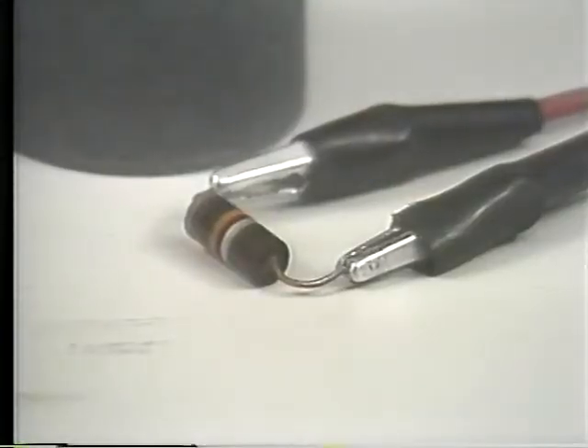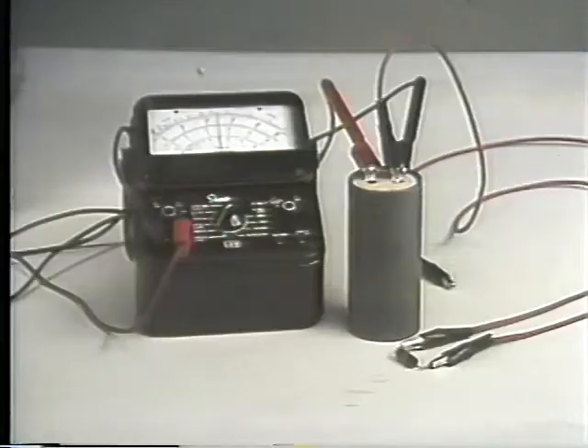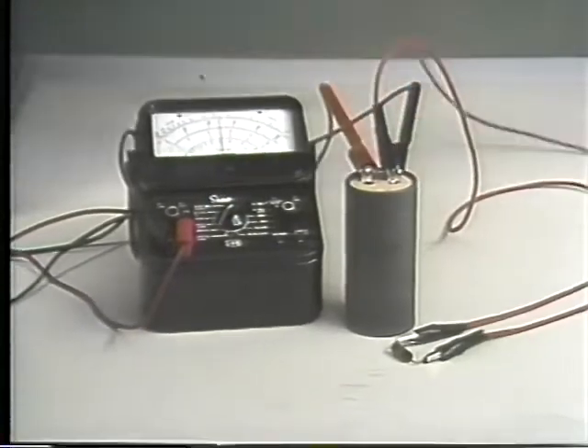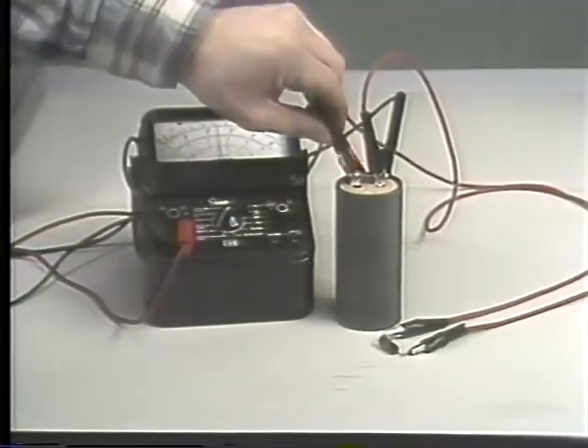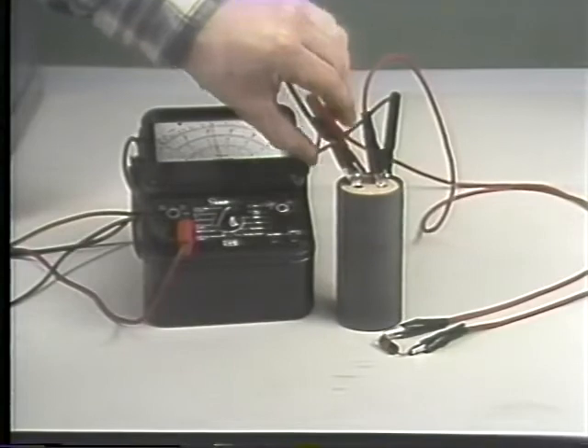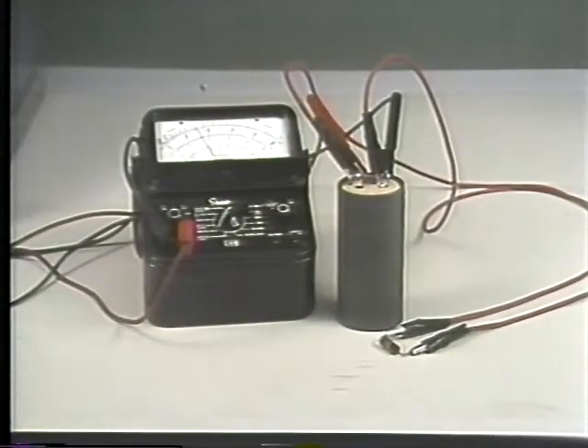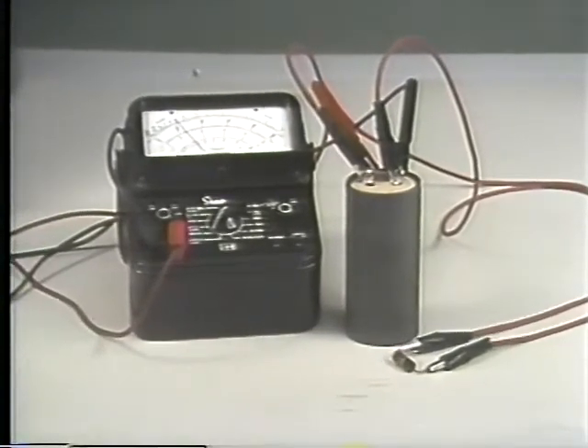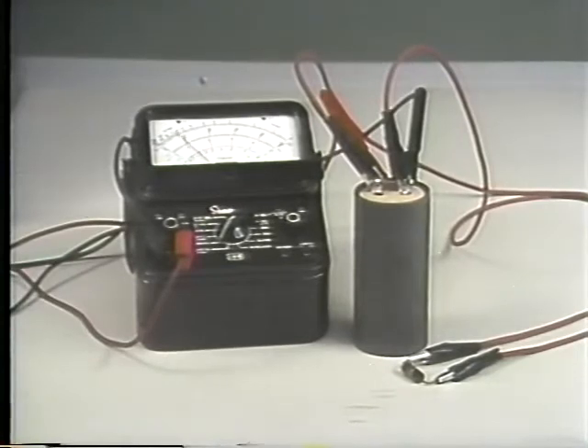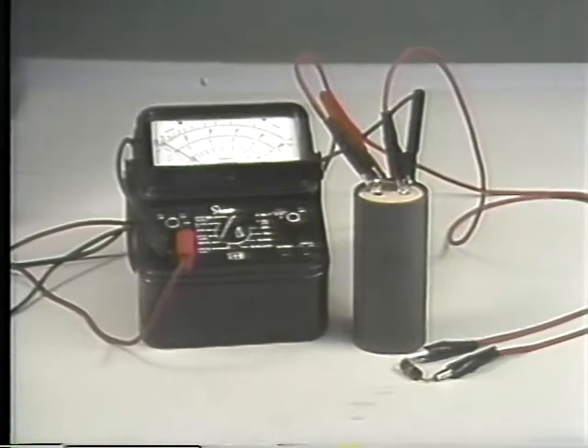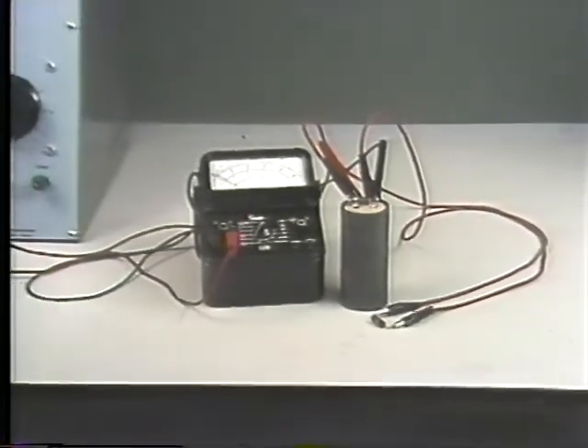This 10,000 ohm resistor will slow down the discharge, so we can see it happen gradually on the meter. Once the resistor is connected across the terminals, the voltage slowly drops. The capacitor will continue to discharge until it's down to nothing. The only safe way to discharge a capacitor is to short it with a resistor of at least 1,000 ohms. Slowing down the discharge reduces the hazard.